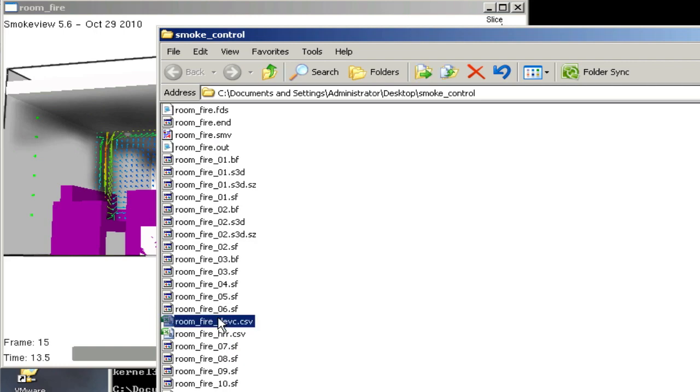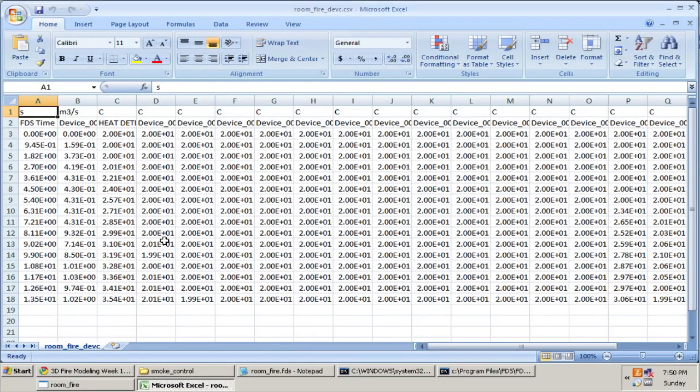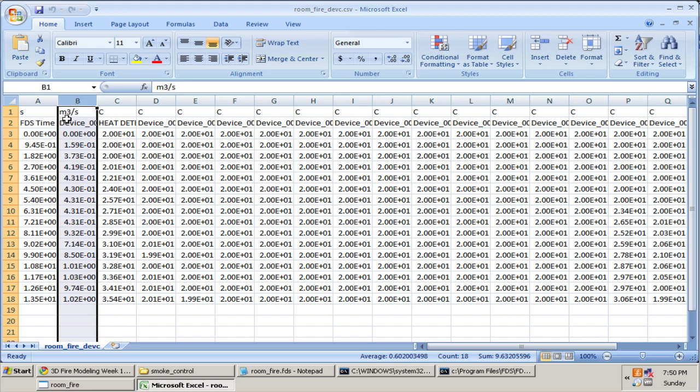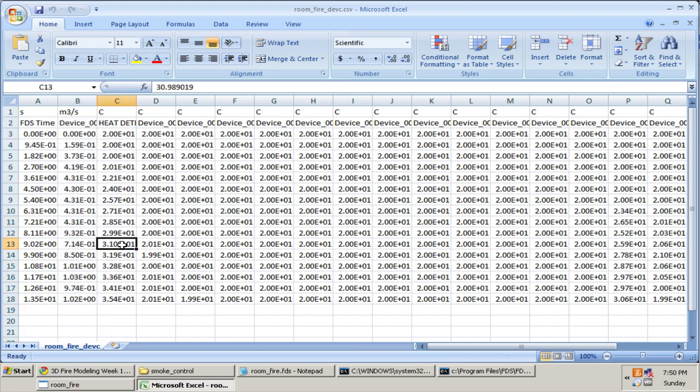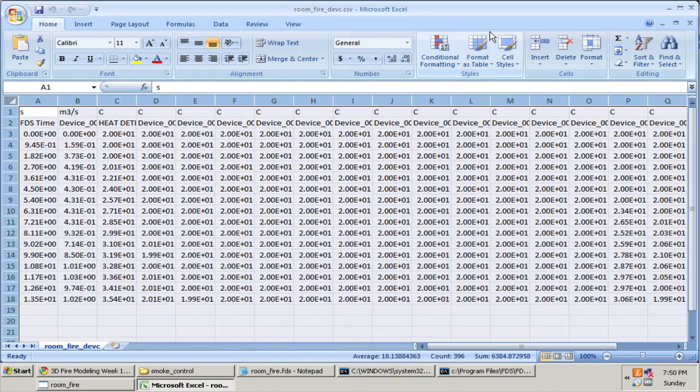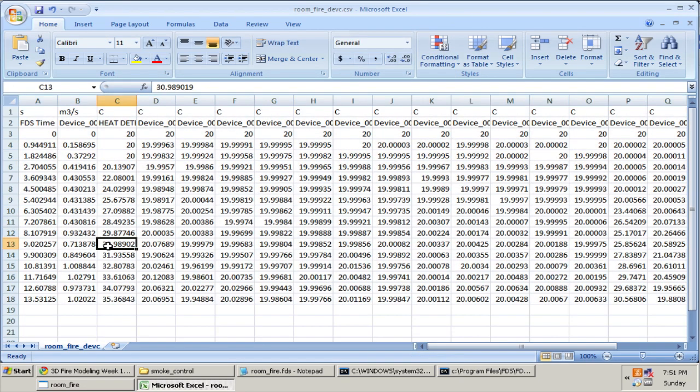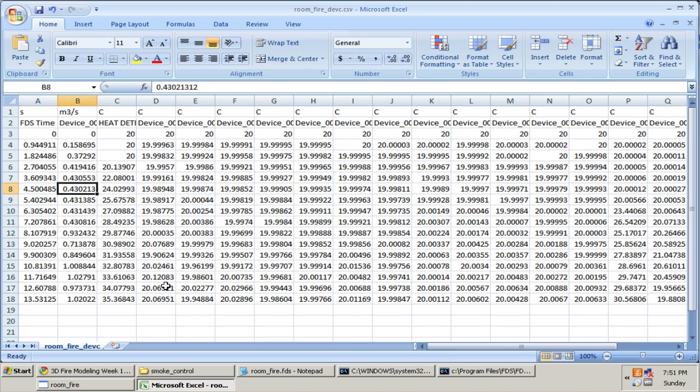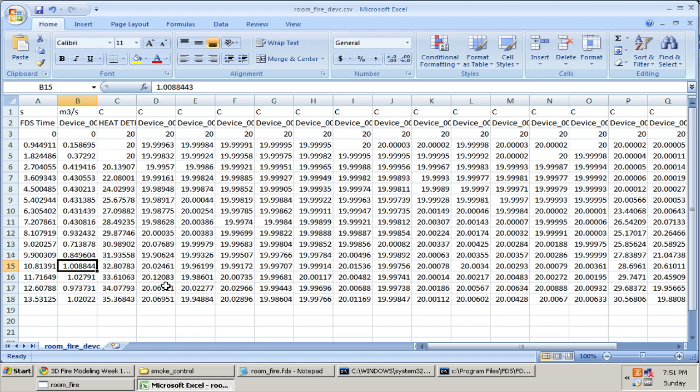The last thing I want to show is the device file. If I open up the device file, I see I have a column for cubic meters per second and also the heat detector. I see the heat detector heat up to about 30 degrees Celsius at nine seconds. I also see here this is actually the flow rate through that integrated device I showed you. At nine seconds you see it hits one cubic meter per second and kind of fluctuates around there, but it is trying to keep the volume flow rate at one cubic meter per second. It's a nice way to plot my fan flow rate to make sure that it is behaving as I wanted.